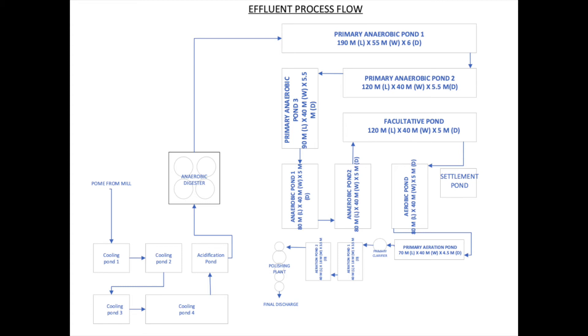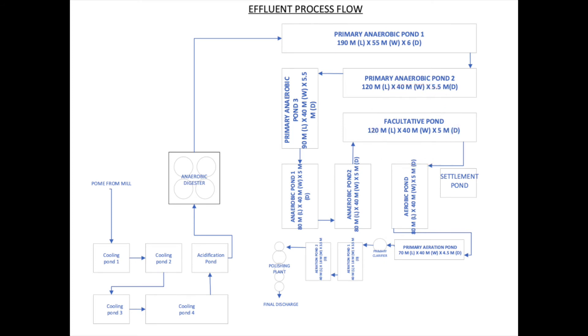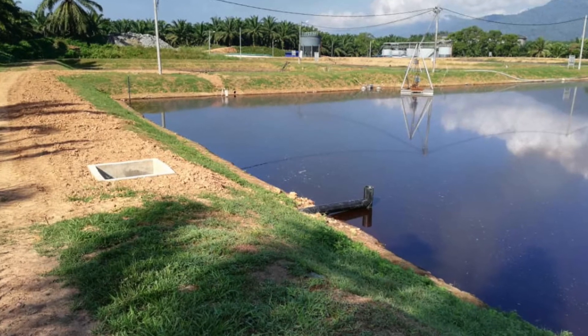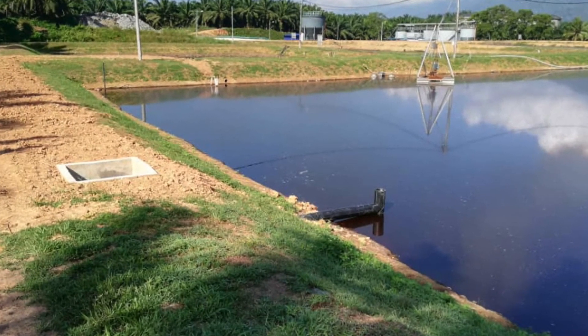The outlet at primary anaerobic pond 3 is not really well placed, so we recommended for it to be shifted to maximise hydraulic retention time. Looking closely at the facultative pond, neither the inlet nor the outlet are well placed to maximise hydraulic retention time. We recommended for the inlet or the outlet to be relocated accordingly. Since then, the sump pit outlet of the facultative pond to the aerobic pond has been relocated.